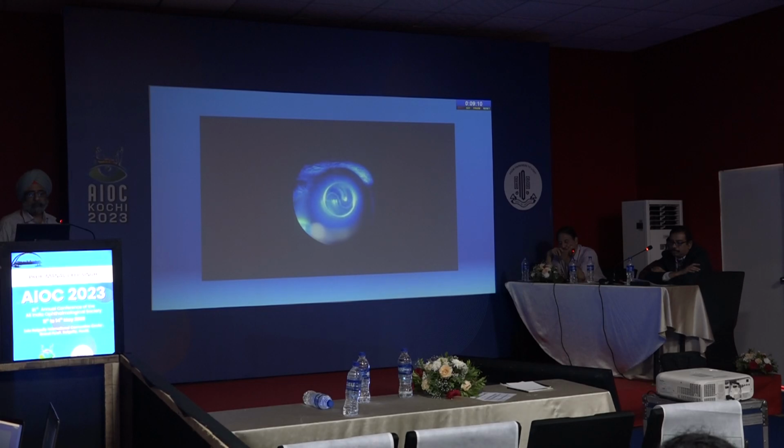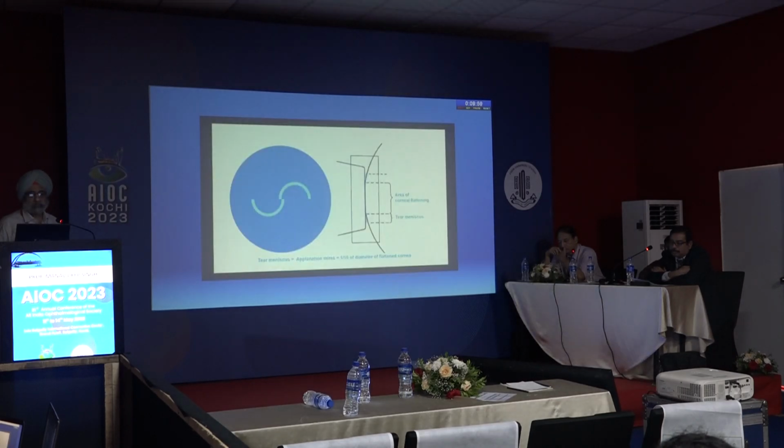When the accurate IOP reading on the drum is reached, the rings are exact semicircles of equal size, vertically well aligned and horizontally interlocked at internal edges. It is essential to emphasize that the thickness of mires should be around 1/10 of the total diameter of the flattened area. Prolonged contact of the prism with the cornea can lead to corneal injury and reduction of IOP, and hence should be avoided.